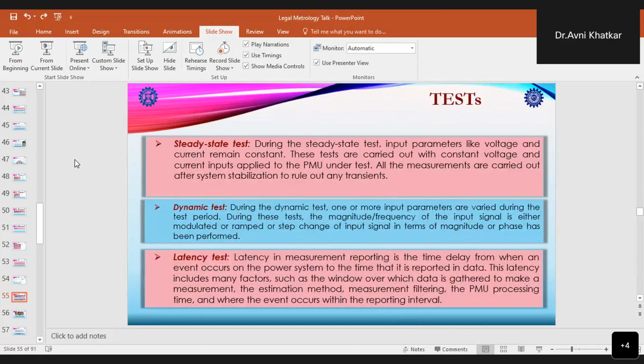When we talk about the tests for PMUs, we undergo different types of tests. Basically, they are divided into three categories, that is steady state test, dynamic test, and latency test. In the steady state test, the input parameters like voltage and current remain constant, and these tests are carried out with constant voltage and current inputs applied to the PMU under test. All the measurements are carried out after the system stabilization, in order to rule out any transients, because we are talking about the steady state test.